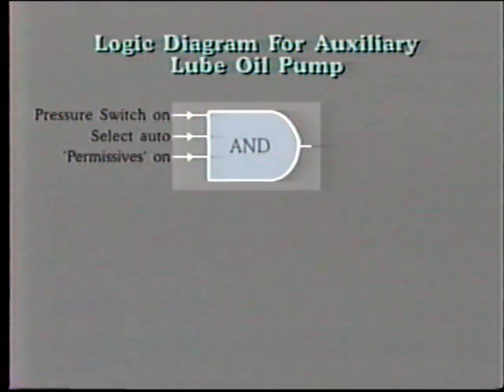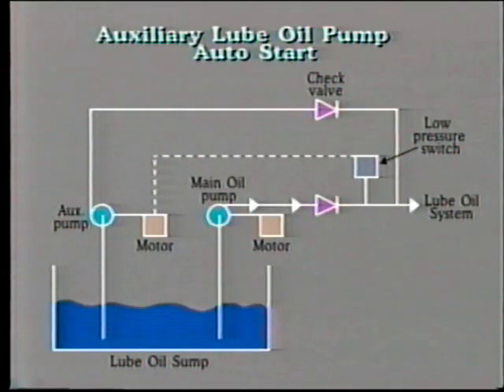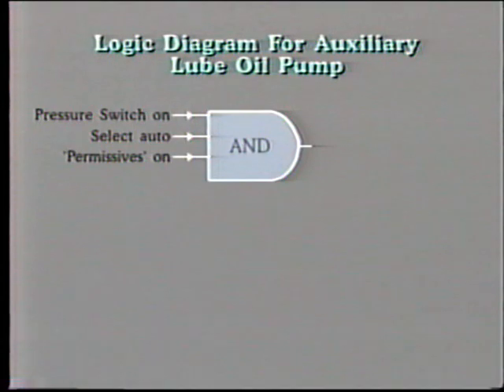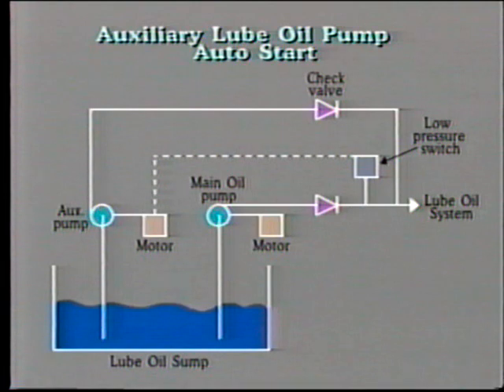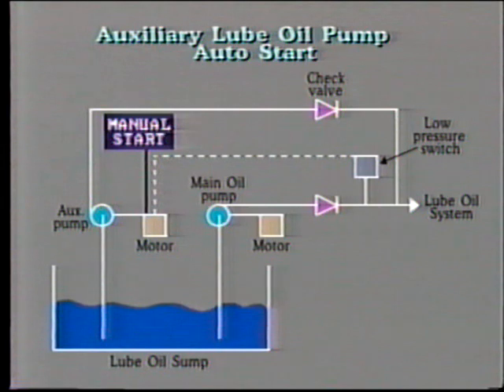The AND gate shows that all three conditions must be met before the pump will start. But in this particular oil system, imagine what would happen when we shut down the gas turbine and switch off the main oil pump. The auxiliary pump will start up and run unnecessarily. So to prevent this, we need to add another AND condition, an ON switch, which is closed when the gas turbine is actually spinning. While the unit is shut down, we may wish to test the oil pumps. In this case, we need to provide a manual start for the auxiliary oil pump.